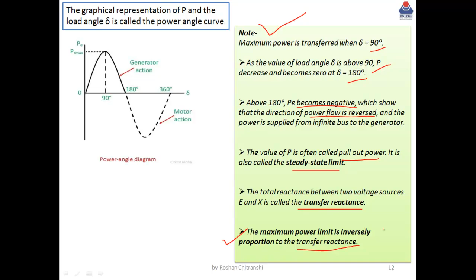So it is very, very important to balance the load angle, and we always balance this load angle with the help of the prime mover as well as the turbine, right? This value of P is often called the pull out power, and this is also called the steady state limit. The total reactance is the transfer reactance, and the maximum power limit is inversely proportional to the transfer reactance. This is also important. If the transfer reactance increases, the power decreases, and if transfer reactance decreases, then power increases. That is why we always plan to design a minimum value of reactance of our line and of our generator at the time of designing or construction.